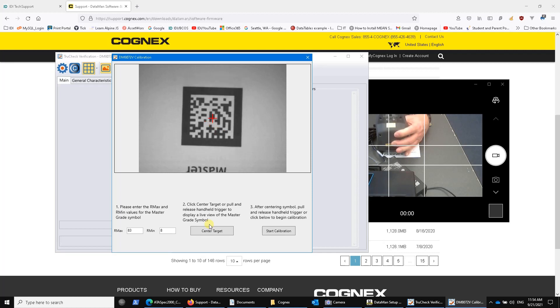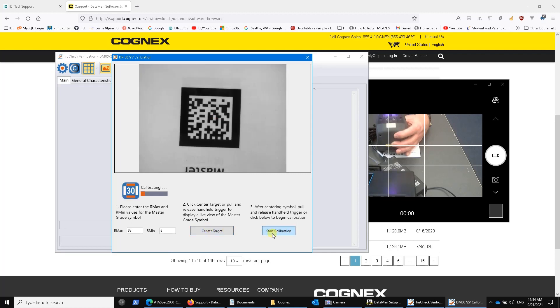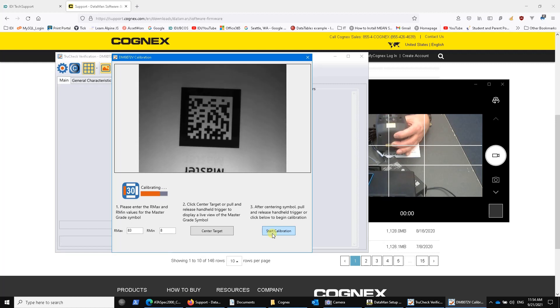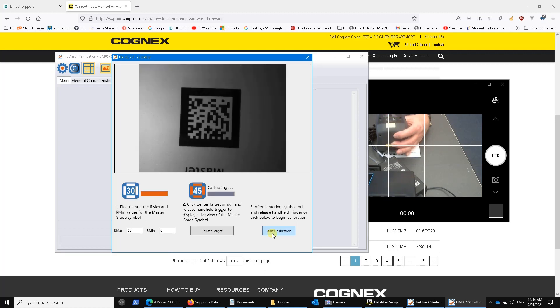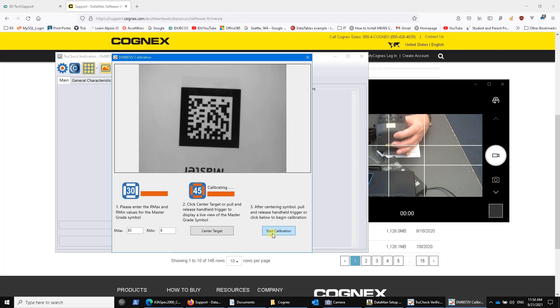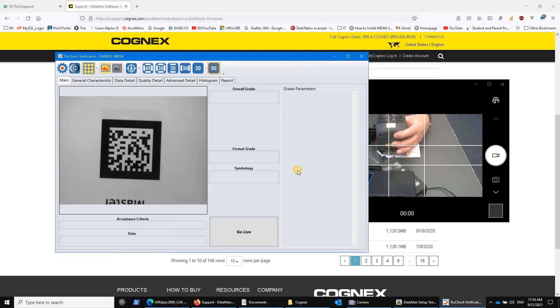And then we can just click on start calibration over here. And it's going to go through each of the angles of lighting that is supported. So we have 30 degree, 45 degree, and 90 degree, right? And then there's all the subcategories. If you've got four quadrants of light, you might also want to do north-south as a pair and east-west as a pair and so forth, right? When it's done, it'll tell you, and now there's a time date stamp associated with that calibration step that we just did.